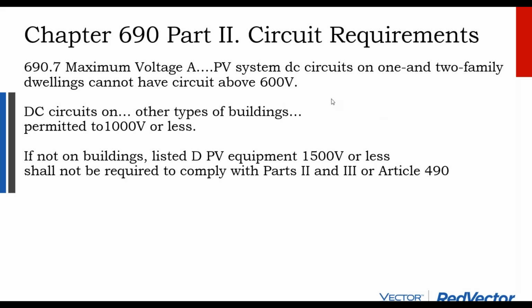Okay, so a couple more things, and we're going to take a 10-minute break. On one or two family dwellings, your circuits have to stay at 600 volts or down. On other types of buildings, 1,000 volts or down, and otherwise you're looking at 1,500 volt circuits.